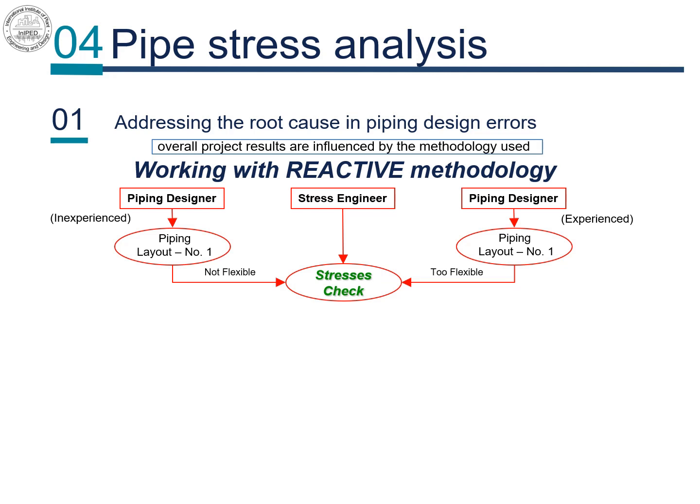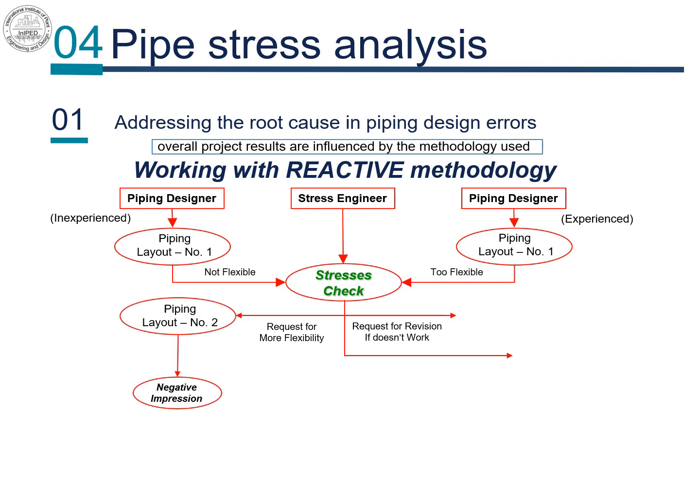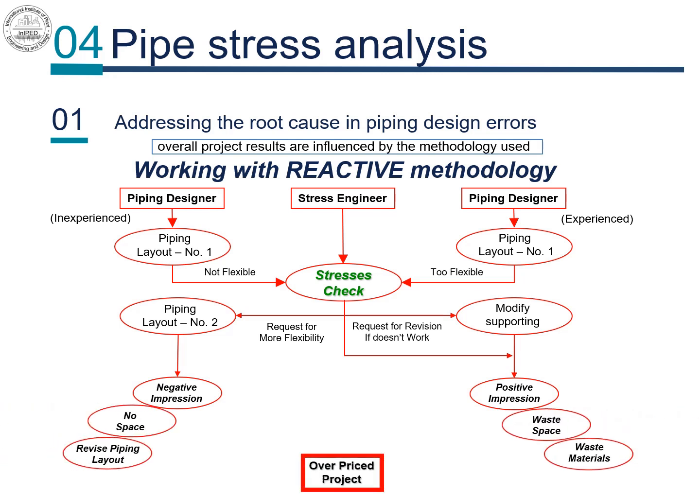be too flexible. In both cases, the stress engineer would be requesting layout rework, the difference being that the inexperienced designer would be given a request to produce a new layout concept with more flexibility, whereas the experienced designer would usually be required to come back with a modified supporting configuration while keeping the same layout. In the end, either side will affect project results in a negative way, with the inexperienced designer affecting the project through a slow process and long schedule, while the experienced designer will affect the project through wasting space and the excessive use of materials.